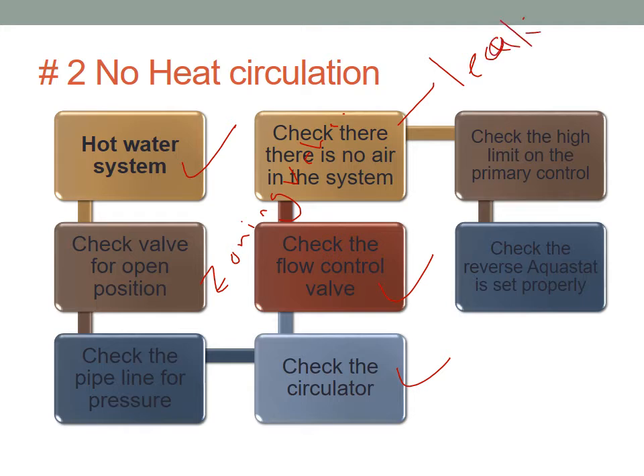Check the high limit on the primary control. Make sure it's set at the right temperature. If it's set at 120, probably it's not going to go more than that and you'll shut off and there is no heat. Make sense? Possible, especially if you have one of those digital ones where you don't see it right away and just keep flipping back and forth.